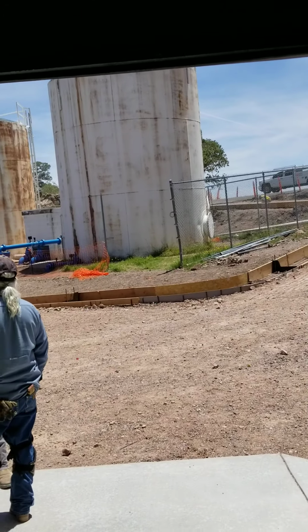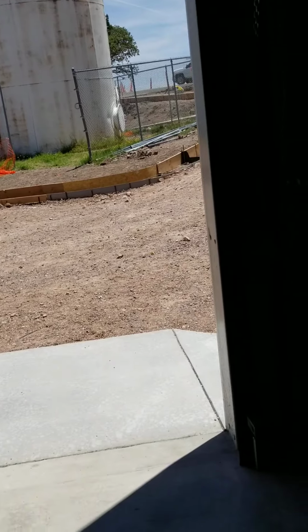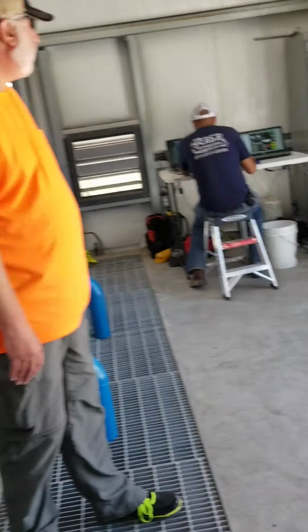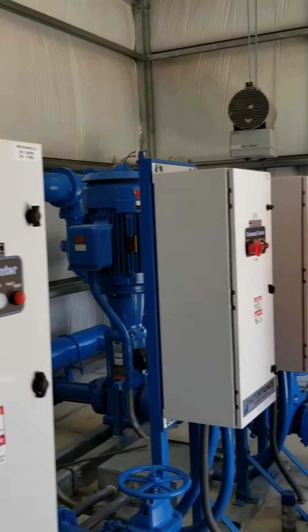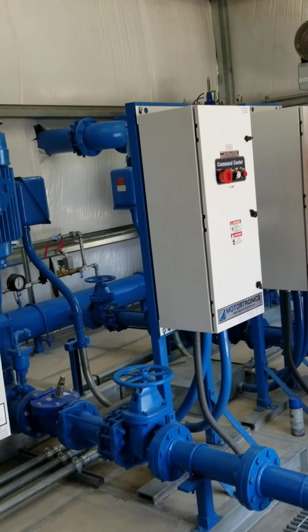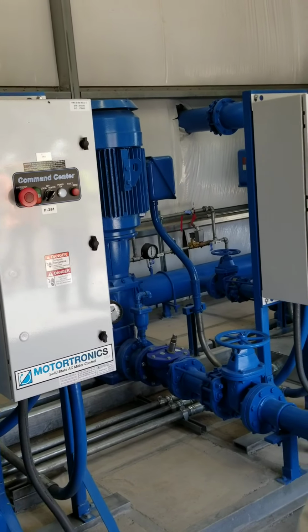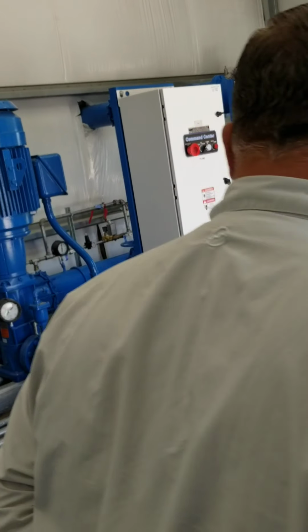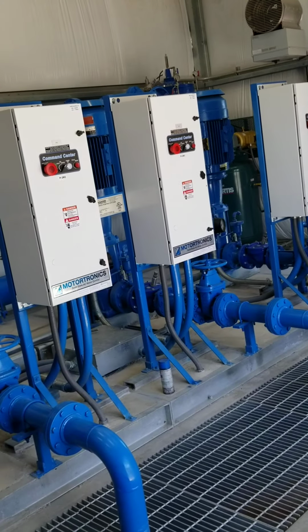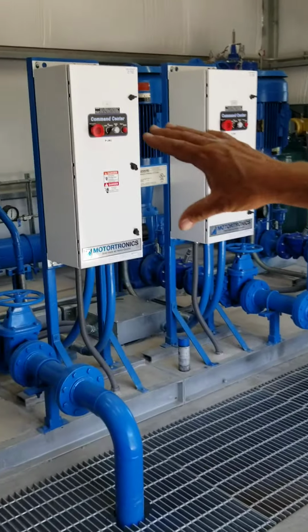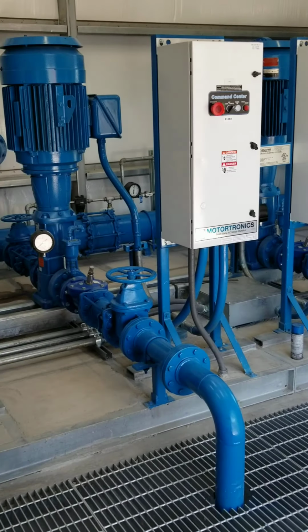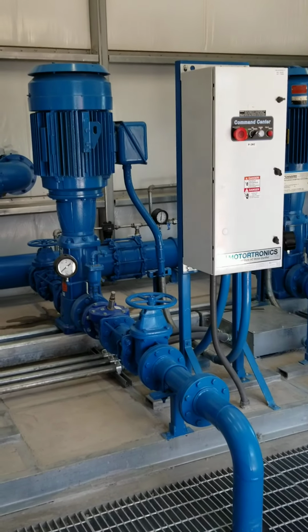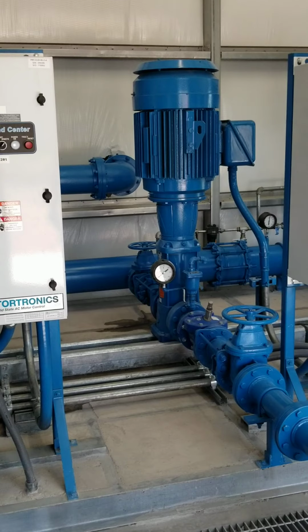We have the tanks coming down, and then they're feeding this system. They go to the back of this header over here, this big blue header, and then through each pump. Each pump has a check valve and a gate valve, and then a soft start. It's not a VFD; it's a soft start. So there's no variable frequency or variable drive in any of it. It's either on or off.